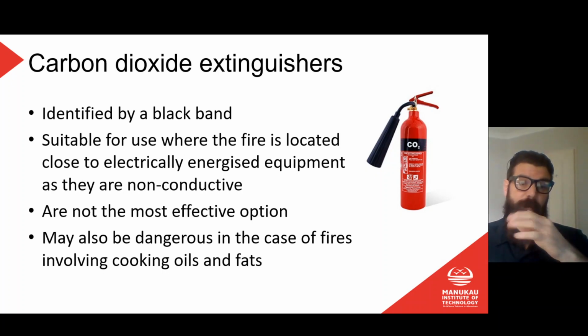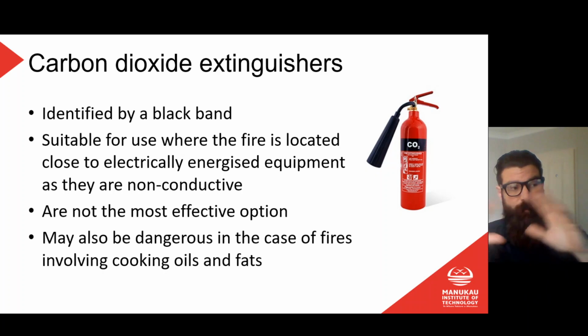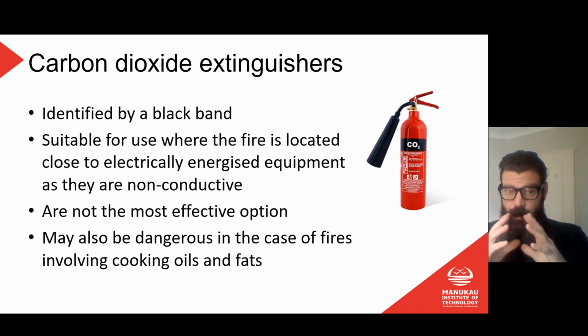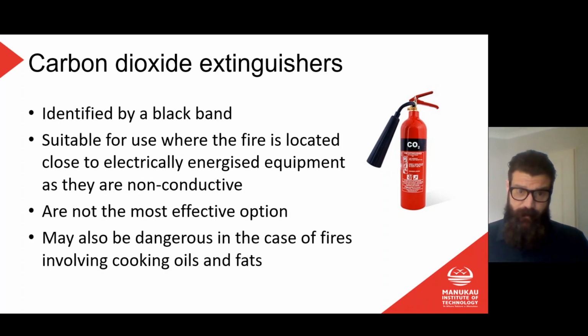So the upside of that is it's good for use on electrical equipment because it's non-conductive. We can spray it onto the equipment, remove oxygen out of that reaction, and then we're not going to leave a big mess like we would with a dry powder fire extinguisher. It's certainly not going to cause us the same amount of issues in terms of the cleanup, because the carbon dioxide will eventually dissipate by itself.